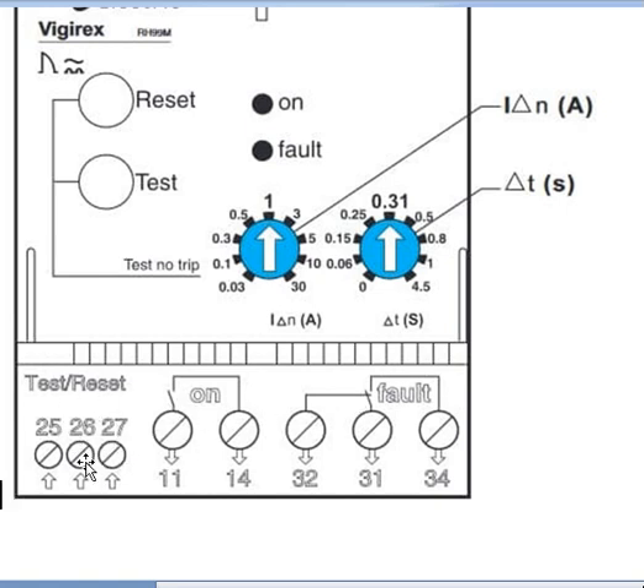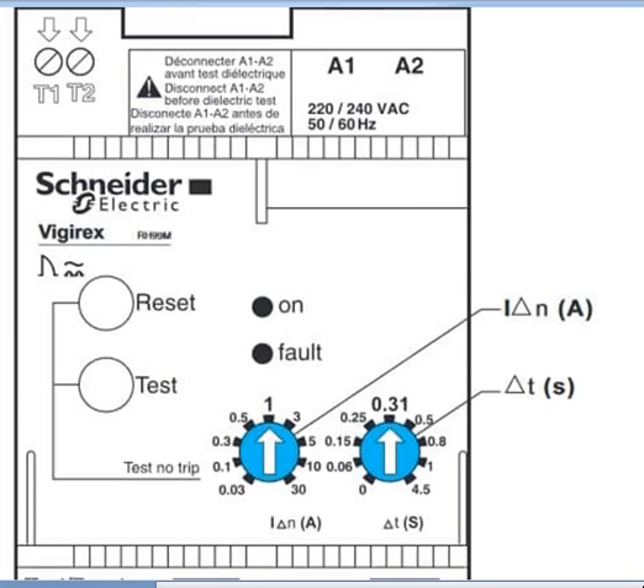And friends, you can trip the relay from far away as well. If you don't want to use the buttons on the top of the relay and you would like to test it from a remote area, you can use these terminals to test or reset the relay from the panel or from remote, far from the panel. So you have to use 25, 26 and 27 for the remote function if you would like to reset and test your relay far from the machine or far from the panel.